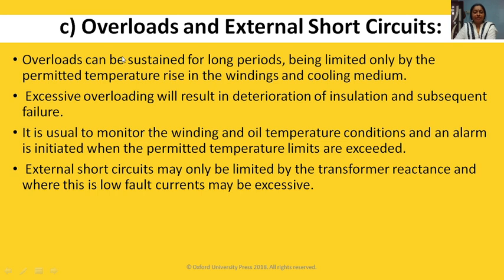Overload and external short circuit, this is the third fault in transformer. External short circuit and overload also cause fault in the transformer. Overload can be sustained for long periods, being limited only by the permitted temperature rise in the winding and cooling medium. Excessive overloading will result in deterioration of insulation and subsequent failure.